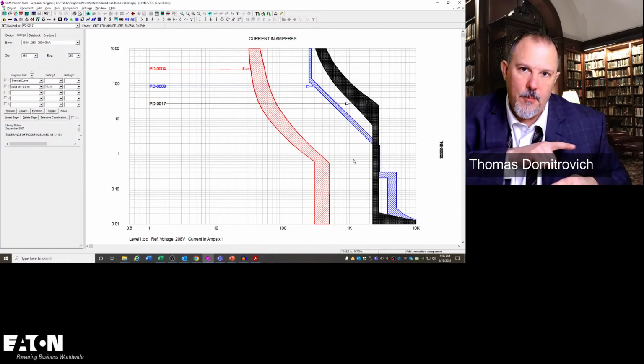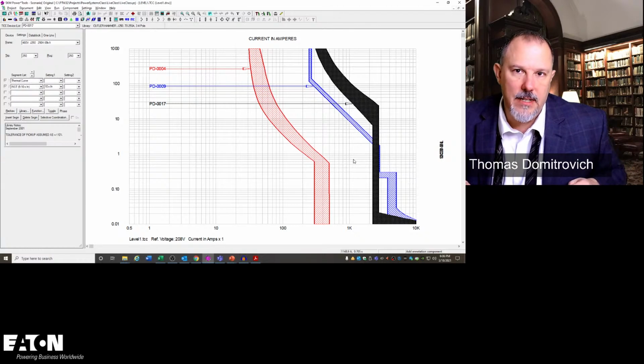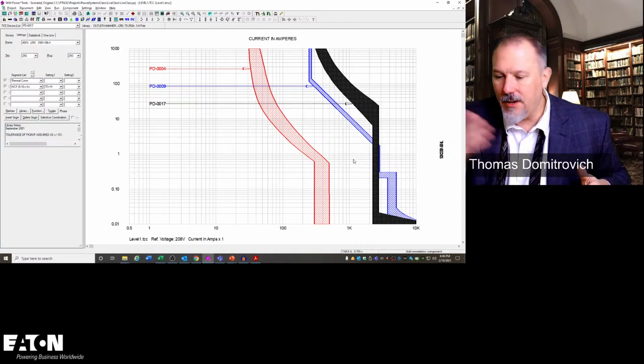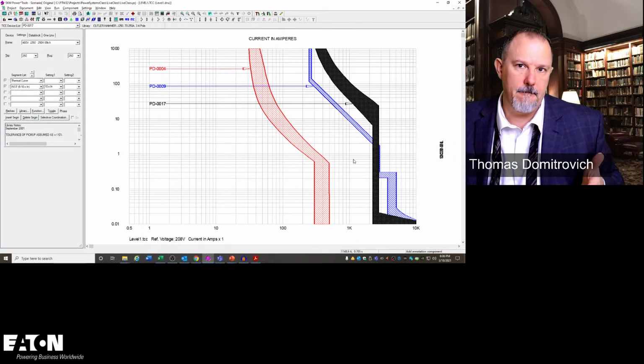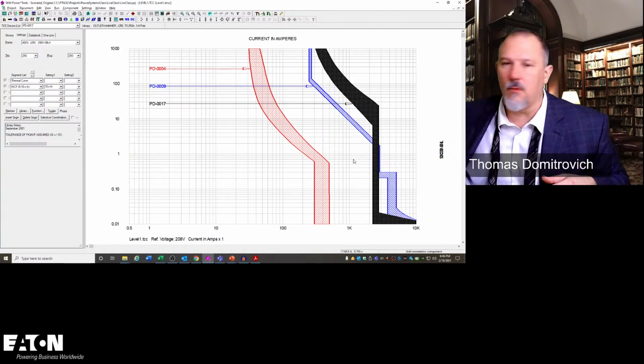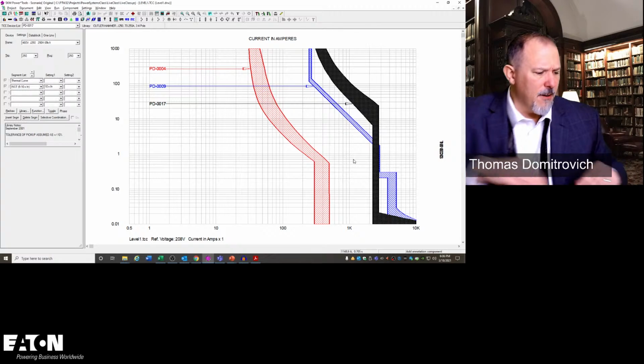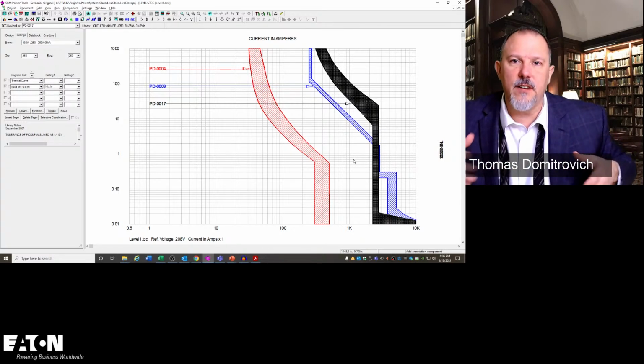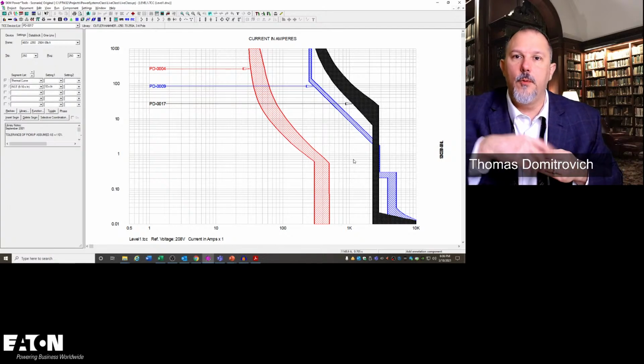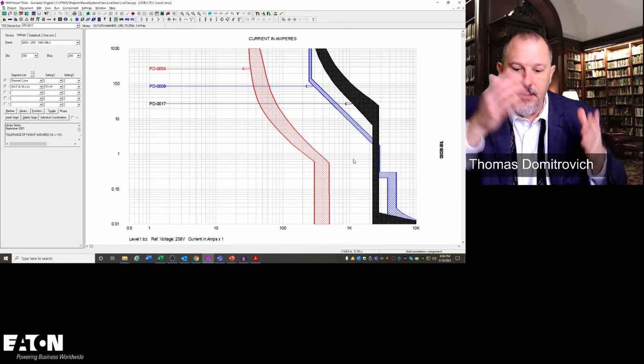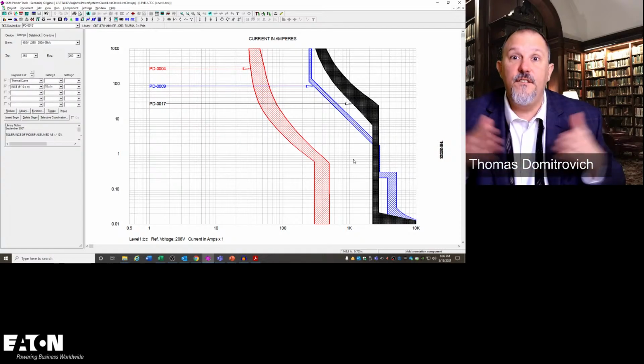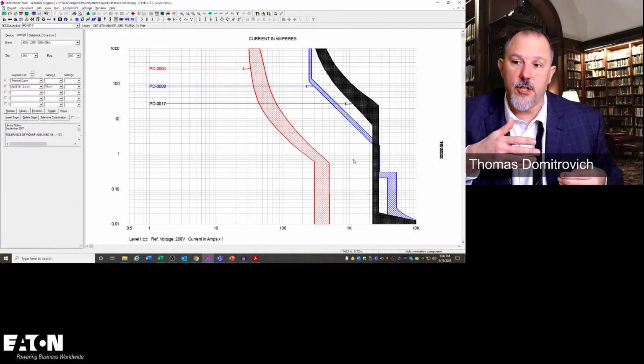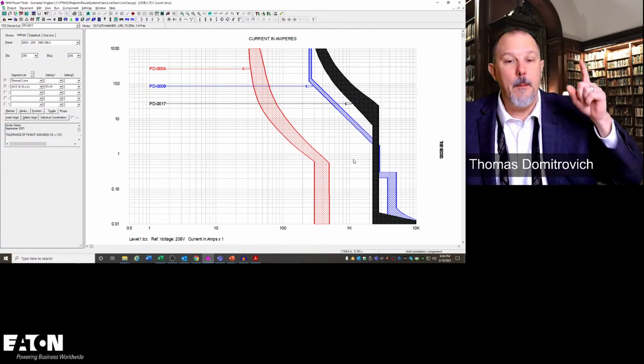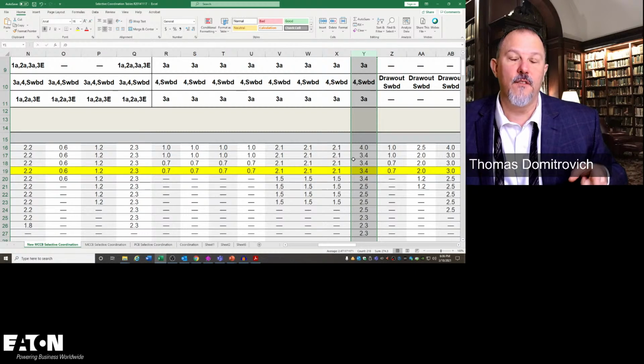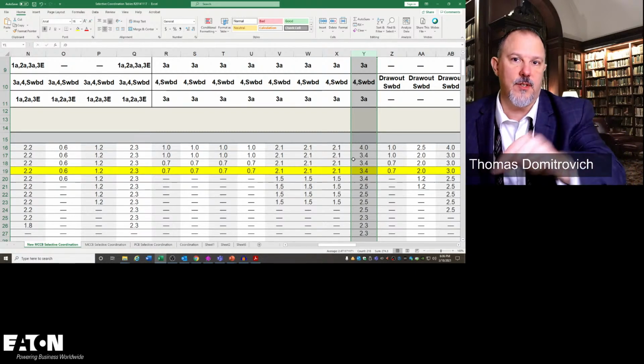In this case, if I put a JD breaker there, yes, it doesn't selectively coordinate to the 8,000 amps, which you will say will never happen in a power distribution system. And so I say, okay, what about the ground fault currents? What do you think the ground fault currents would be? Are they 8,000 amps? No, they're not 8,000 amps. What are they? If you look at the red book and stuff like that, they're like, we'll say 60%, 70% of the bolted fault current, whatever that number is, or your arcing ground fault. You look at your arc flash, your 1584 calculations. I say, okay, you're saying it's around 60 or 80%. Let's say 50%. Let's just be a little bit more conservative. And I'm going to cut 8,000 amps in half as 4,000 amps. Based upon my tables, you're still going to trip for the most common fault in a power distribution system.